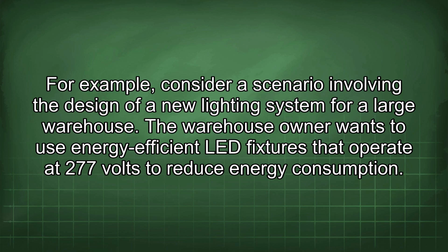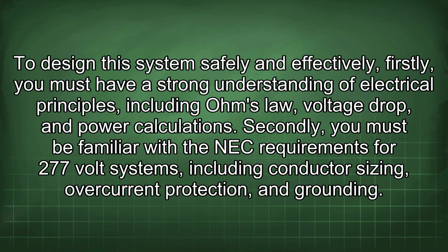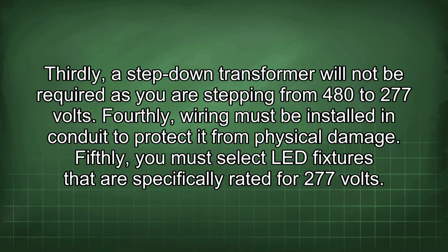For example, consider a scenario involving the design of a new lighting system for a large warehouse. The warehouse owner wants to use energy-efficient LED fixtures that operate at 277 volts to reduce energy consumption. To design this system safely and effectively, firstly, you must have a strong understanding of electrical principles, including Ohm's law, voltage drop, and power calculations. Secondly, you must be familiar with the NEC requirements for 277-volt systems, including conductor sizing, overcurrent protection, and grounding. Thirdly, a step-down transformer will not be required as you are stepping from 480 to 277 volts.